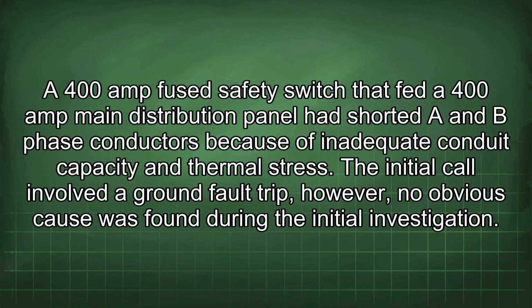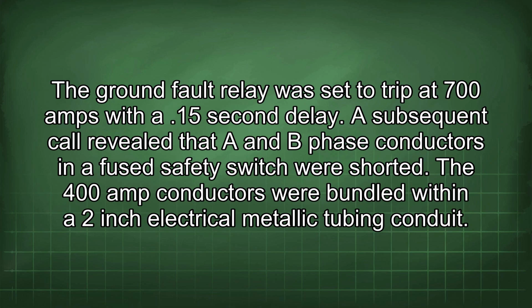A 400 amp fused safety switch that fed a 400 amp main distribution panel had shorted A and B phase conductors because of inadequate conduit capacity and thermal stress. The initial call involved a ground fault trip, however. No obvious cause was found during the initial investigation. The ground fault relay was set to trip at 700 amps with a .15 second delay.